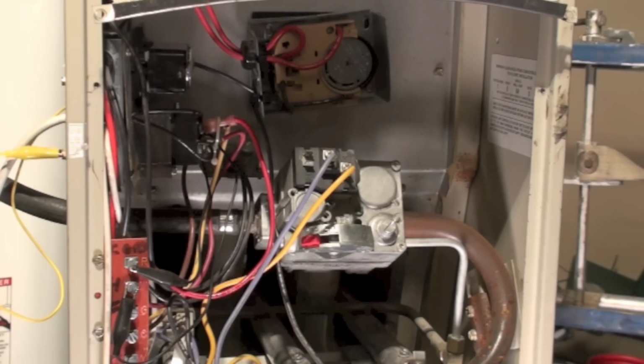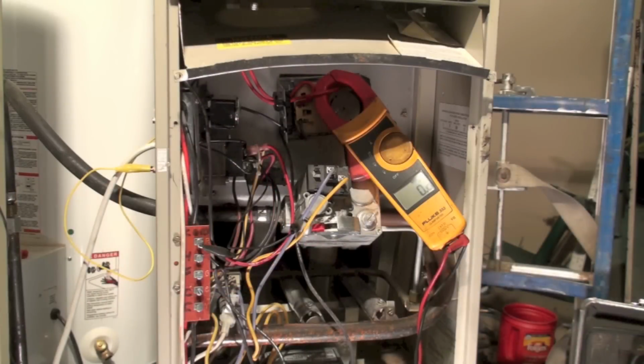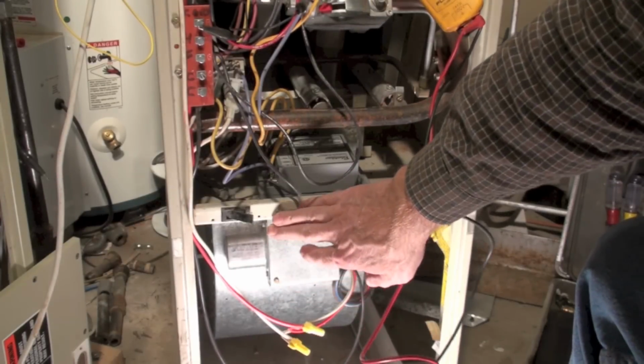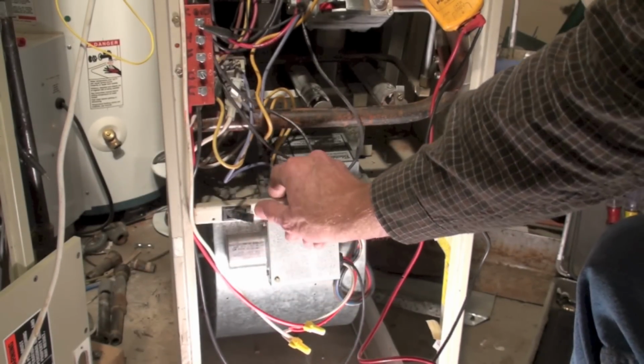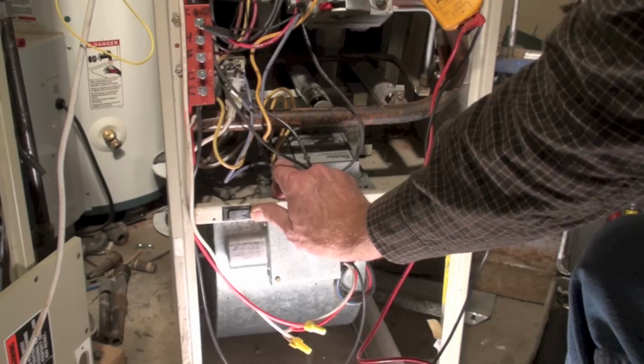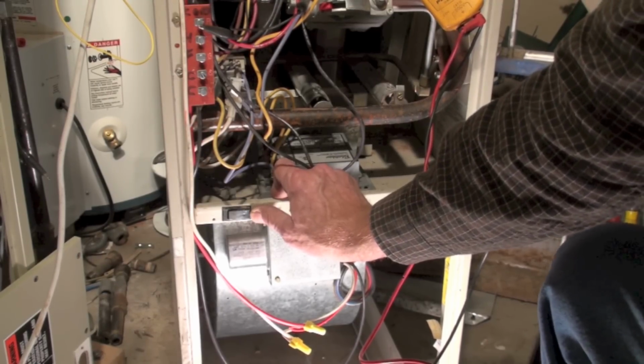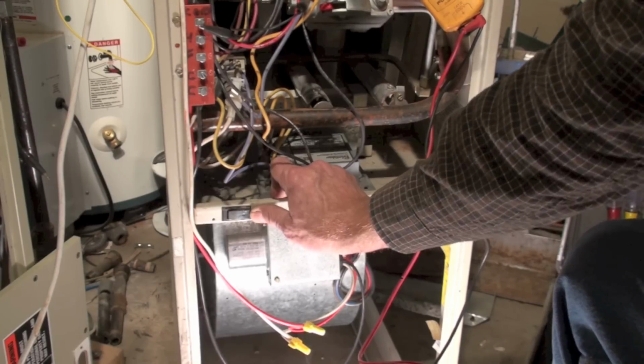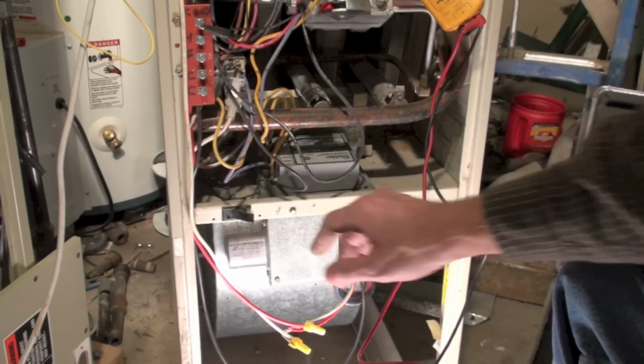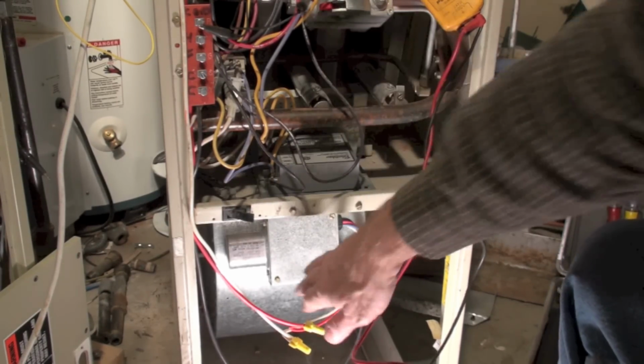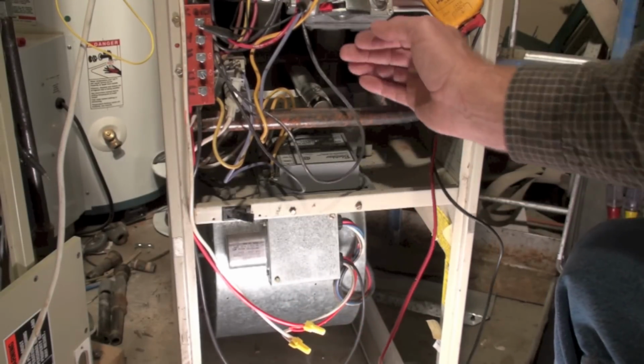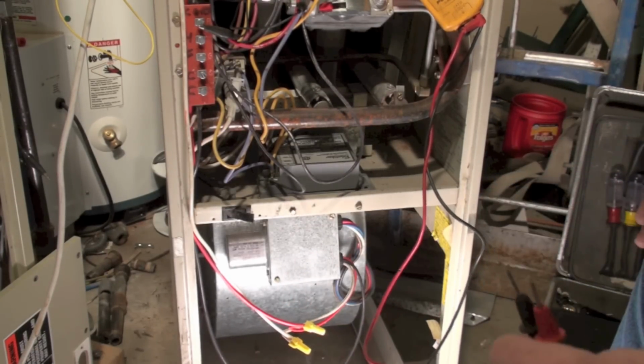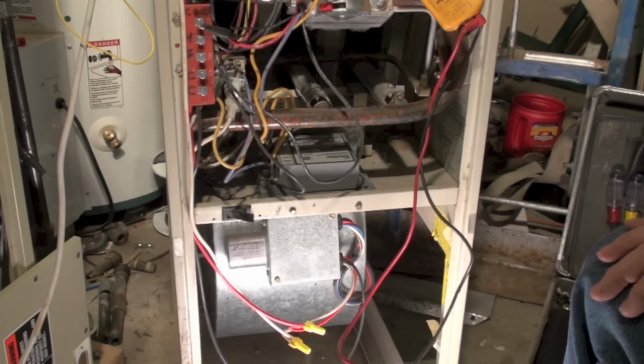But I thought I'd do a little bit of a troubleshoot with this one because it's a little bit different than some others, and we'll start a little series here. Okay, I've got a meter set up in this thing, and the bottom cover should be on because there's a door switch right here, and you're going to have that door switch closed. You can close it, tape it or clamp it if you want to. It's best to have the bottom door on though, because it tends to upset the flame. This pulls a negative pressure when it starts, so it could actually pull a flame out somewhat. So probably have that bottom part on.